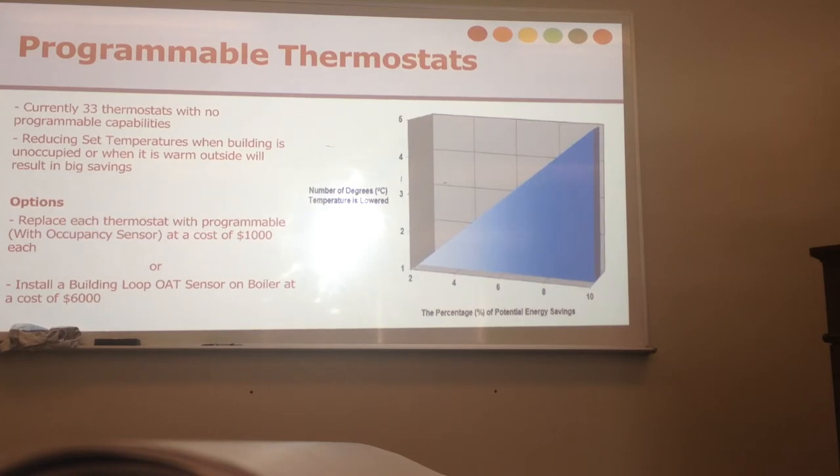And then if you lower 2 degrees, save 4%, all the way up to 5 degrees, you can save up to 10% of your total potential energy savings for a year. And you don't want to, 5 is basically the limit. You don't want to lower too much, you don't want to go too much lower than that because then you get into the condensation problems on the windows and that kind of thing. So but if you lower every thermostat by 5 degrees, you can save up to 10% of total energy savings. I don't have an actual number that they save. Well what we can do is we can do an example of, I can get the first years to do a hot 2000 analysis of whatever home they have. This chart actually came from my last check-in or whatever. It had an example of using 10, saving 10 gigajoules. It was just a good example. It's pretty clear, so I could throw that in.